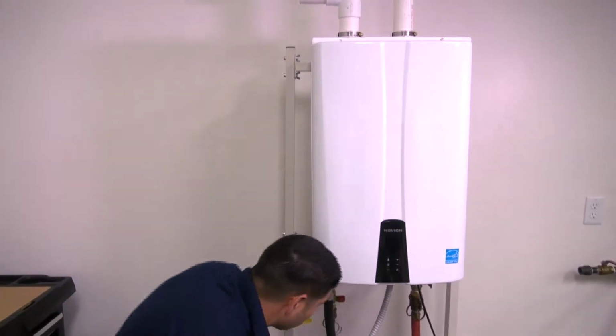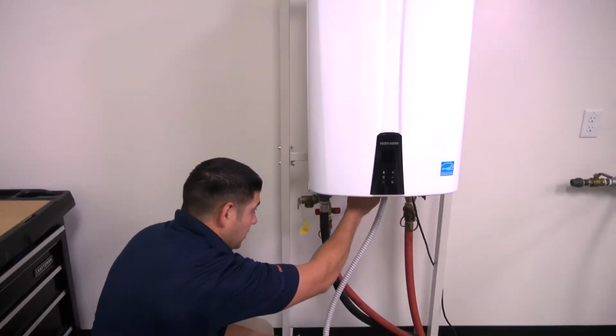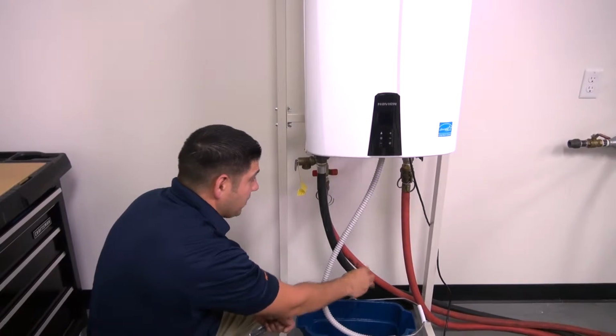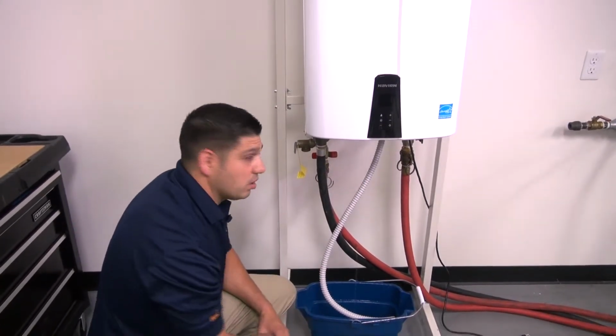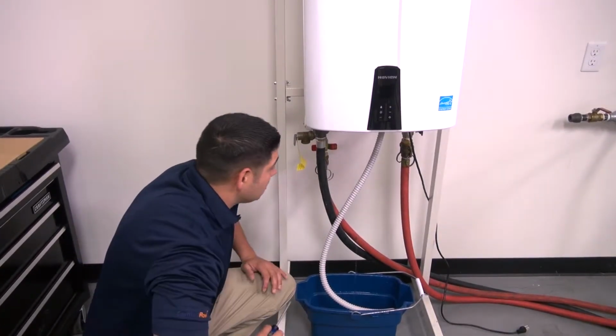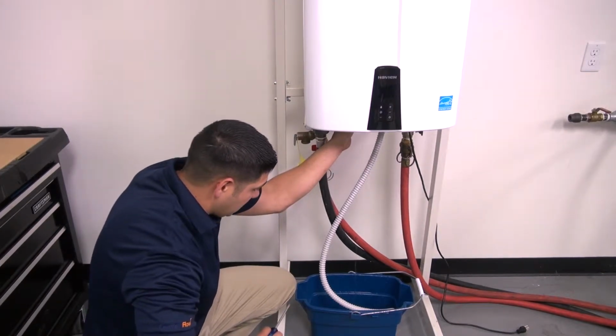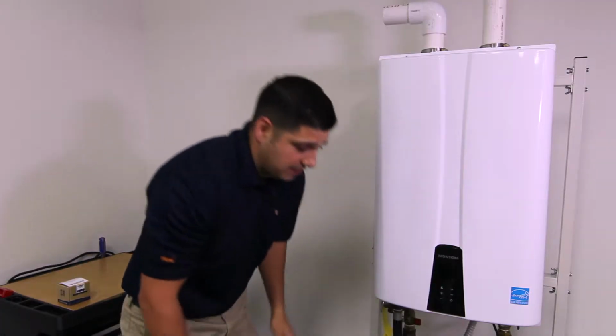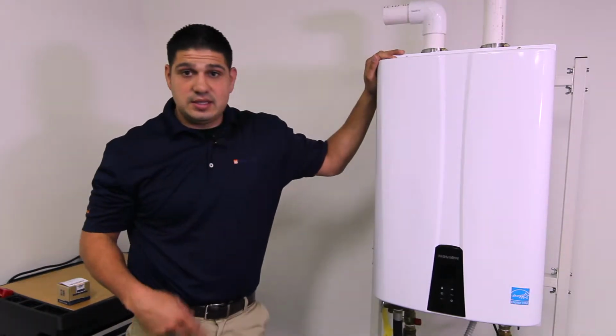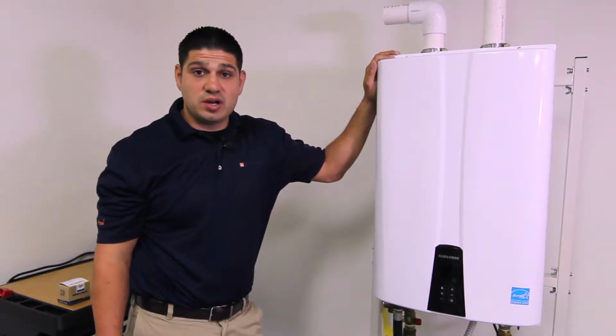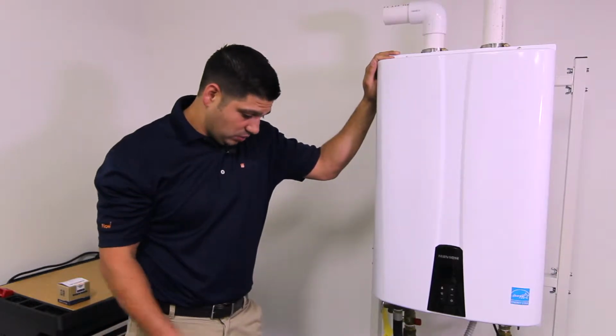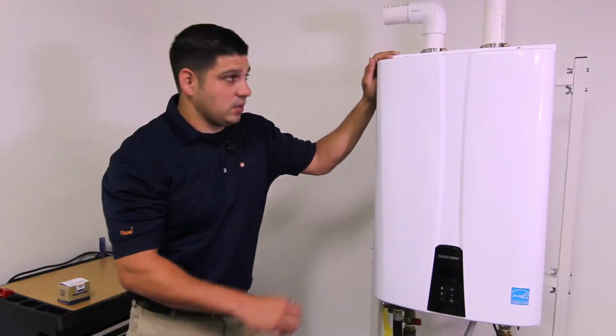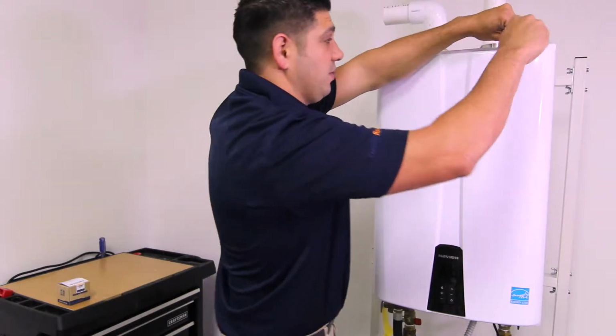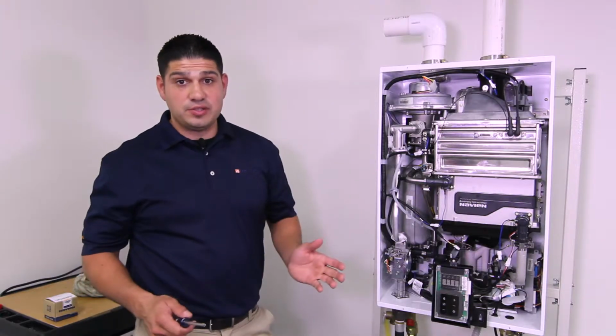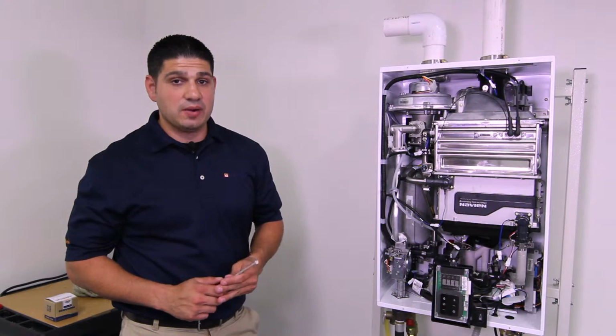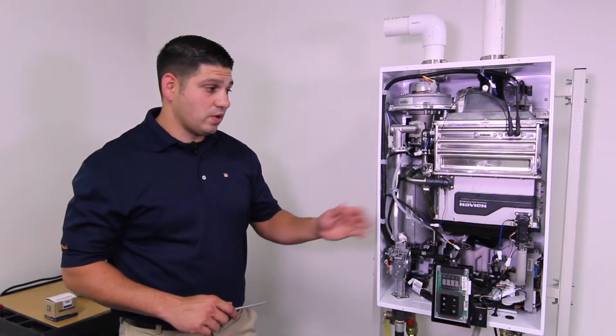Once we do that, we're going to go ahead and drain the unit down by opening your bleeder underneath the pump. So just let that drip down. Make sure you have a bucket, any rag available, because there will be some water. You may have some spills. You don't want to cause any damage to the home. So this unit's drained. As it's draining, what I'm going to go ahead and do is start taking off my cover. Now that we've properly drained down our unit, we've disconnected the power and shut off our gas, we're good to start removing our flow sensor.